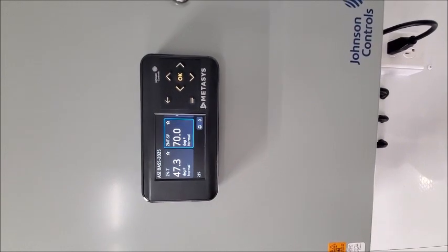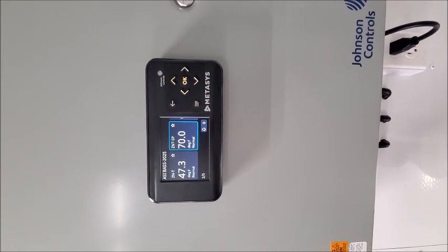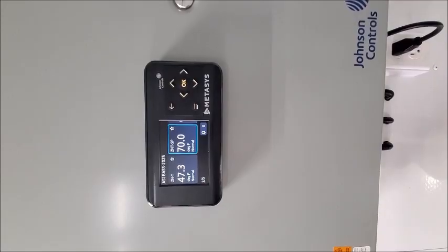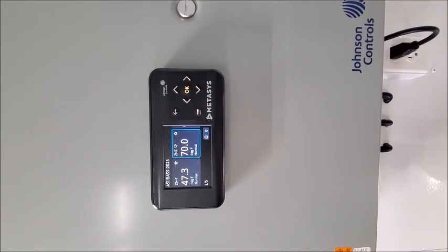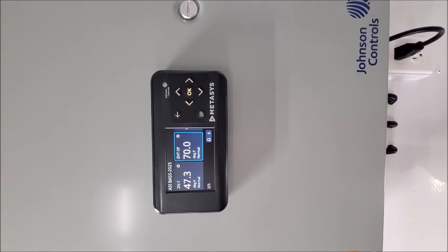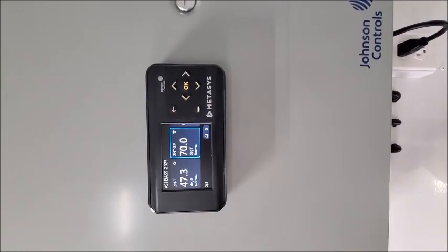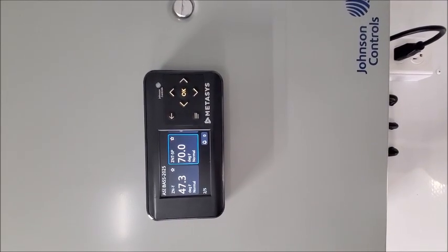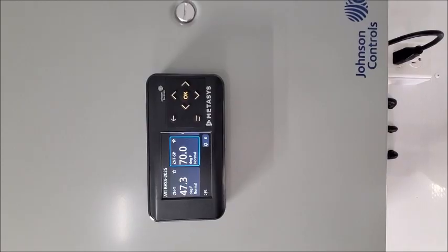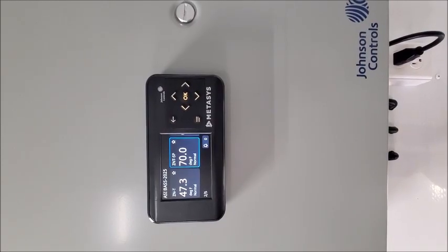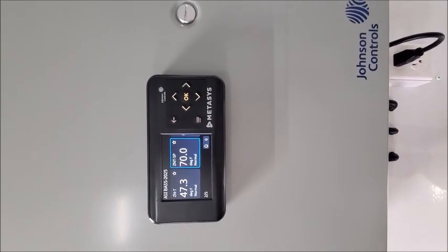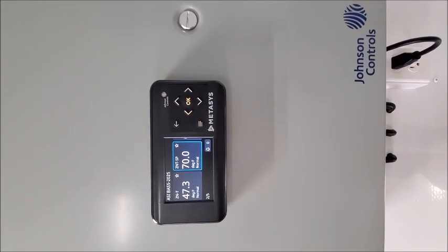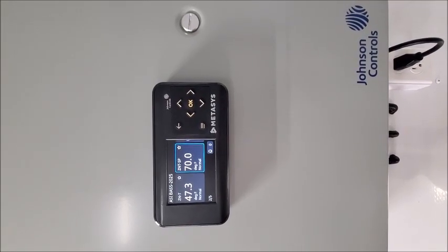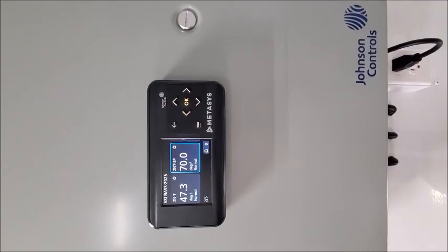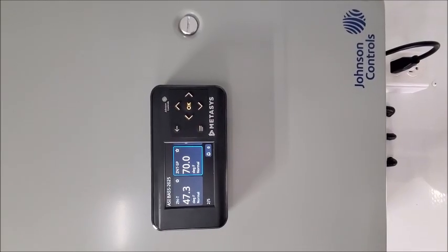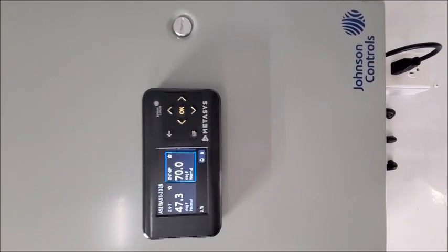A user adjustable temperature set point, ZNT-SP, on the controller can be entered on the controller pad and should be the same as the thermostat setting for the heat pump. This set point will determine when and what actions the motorized louver should take to maintain the internal cabin temperature. The user can scroll to see the status of each element in the system: ZNT, ZNT-SP, CAD, IDD, and ODD.